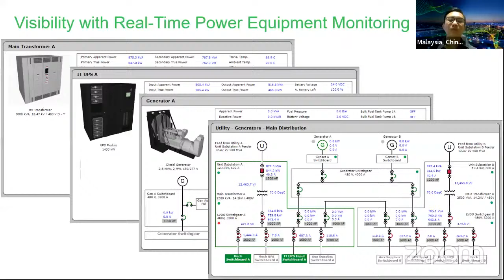This is more on addressing the risk of power disruptions and fire risk. Most of the time, when we have an electrical transfer from one point to a load, there will always be heat generation. This heat generation is not just one of the problems, but because of the frequency of the electricity, there is also the problem of hotspots on loose connections.